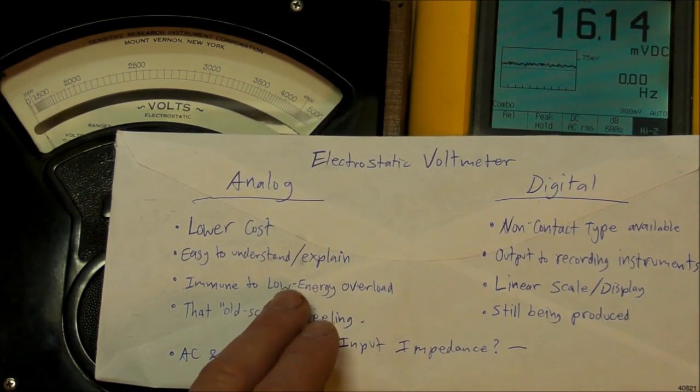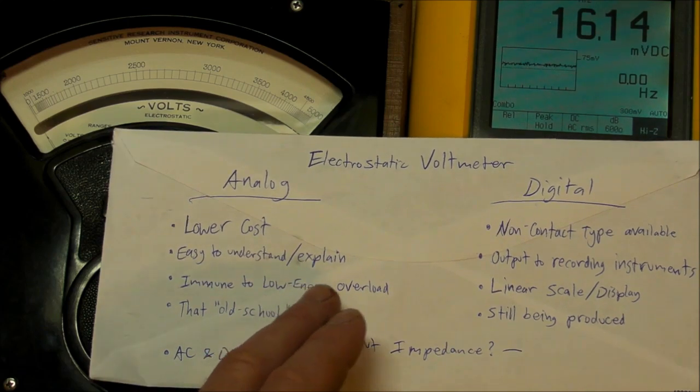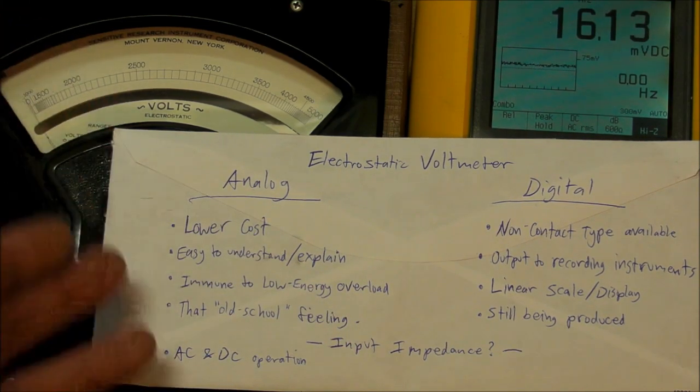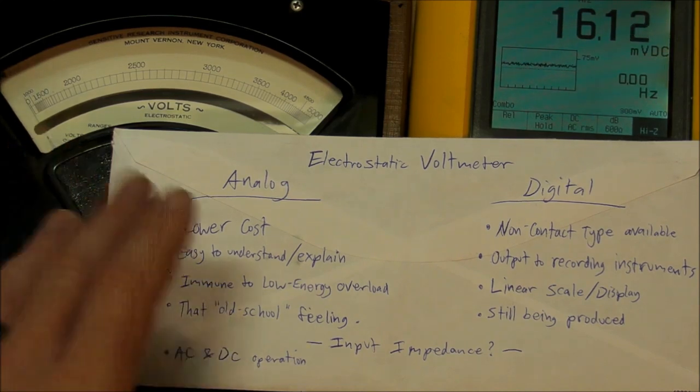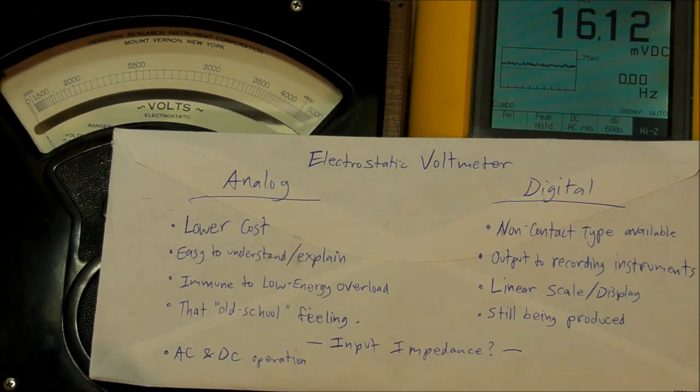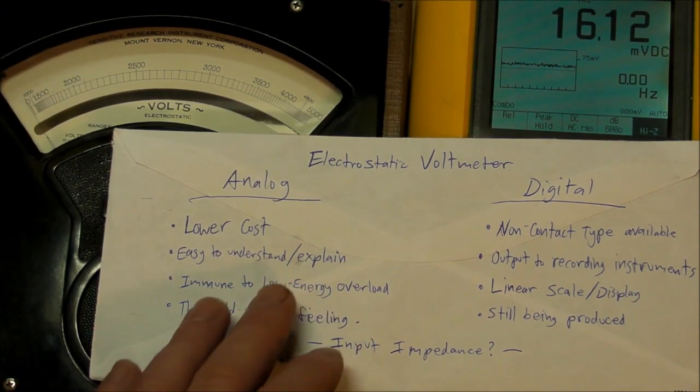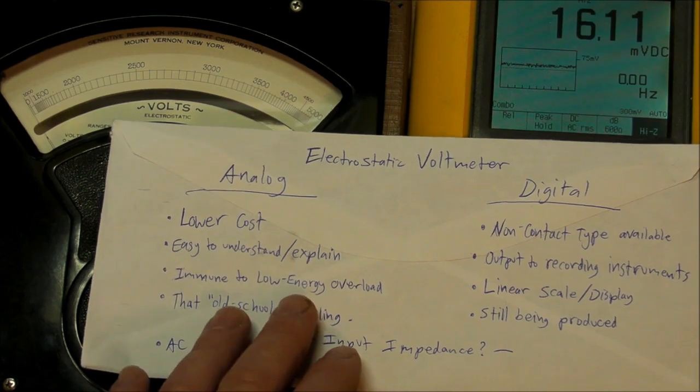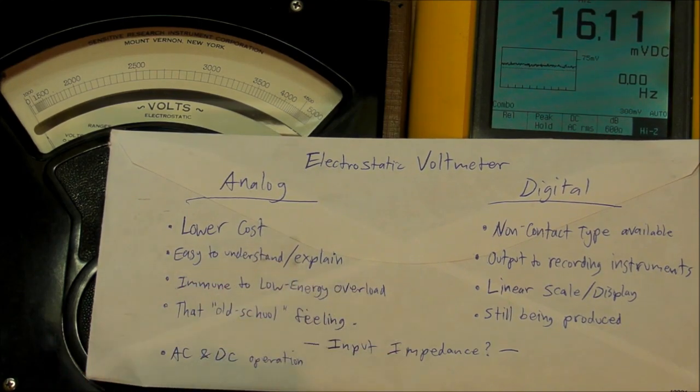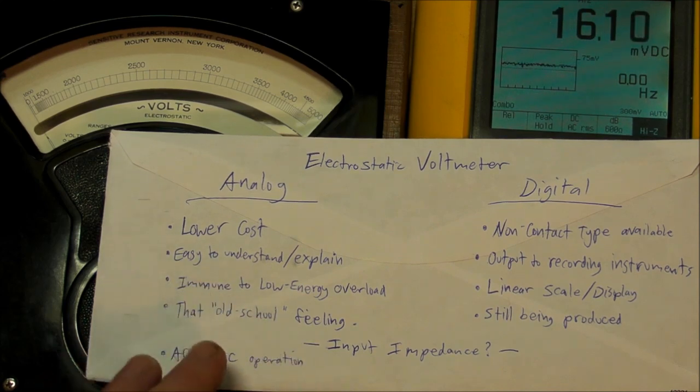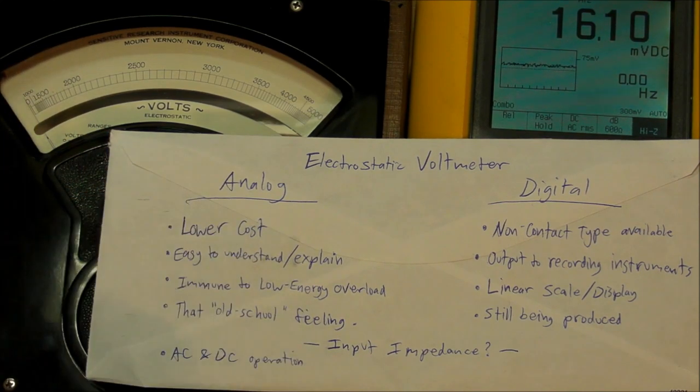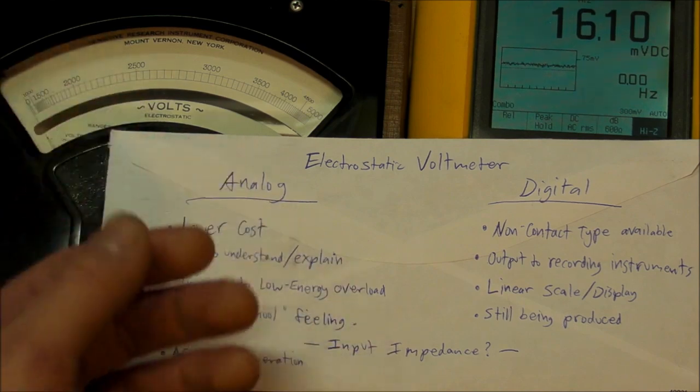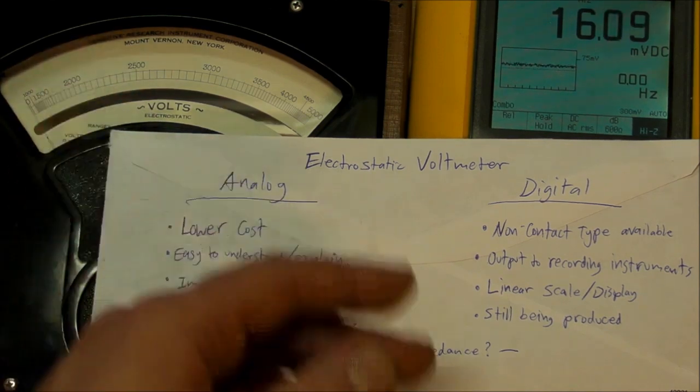Also with digital they very often come with the option to output an analog signal to recording instruments, any kind of analog voltage that's proportional to what it's actually reading. And also linear. Digital meters are pretty much going to be linear scale and we saw already how very non-linear this thing is.